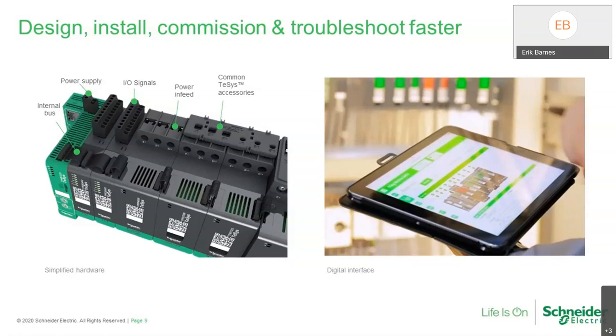Think about the commissioning end. Let's say you've set up your island and you get on site and you realize that maybe the undervoltage or the undercurrent protection setting is a little too sensitive. No problem. Just connect to the island, find the setting, make the adjustment real quick and save it, and you're done, right? So it's very simple, very easy to commission and later fine-tune things in the field without having to mess with the PLC program, which is very nice.